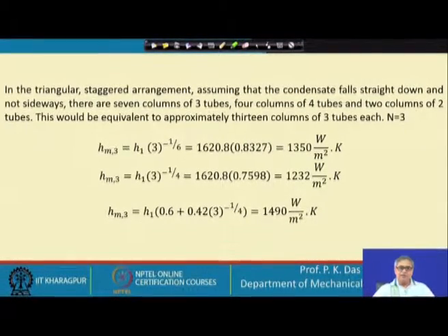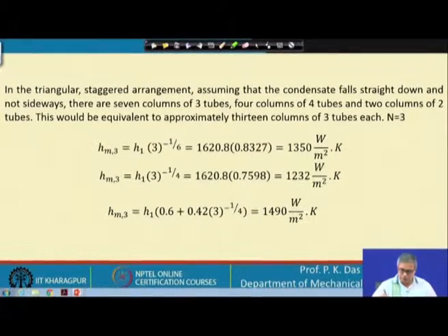In many cases, if there is no other reason, people will prefer to have a staggered arrangement. A staggered arrangement gives a compact design. In a small volume, you can pack more tubes. That is the first thing. It gives a higher rate of heat transfer. That is another thing, and in case of condensation, it gives lesser inundation of the condensate film. So, with this message, let us move to the next slide.